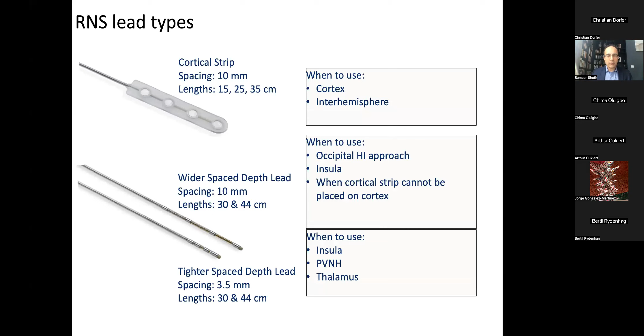One more thing on this, the overall length of this electrode comes in 2 sizes, 30 and 44 centimeters. I tend to use the 30 because otherwise there's a lot of excess wire just floating around subgaleally, which is annoying. But there's an important point to that, which I'll talk about here. So the 30 centimeter lead is good in terms of leaving the least excess wire floating around subgaleally that you have to tuck under and get out of the way.